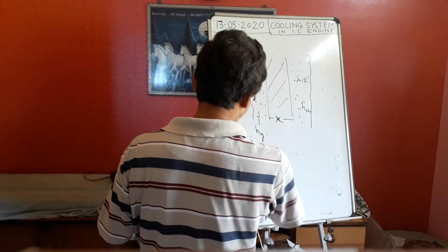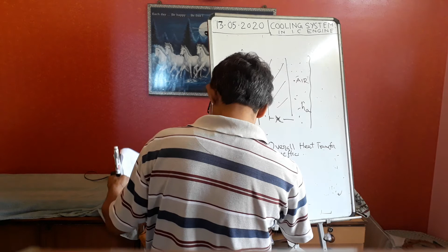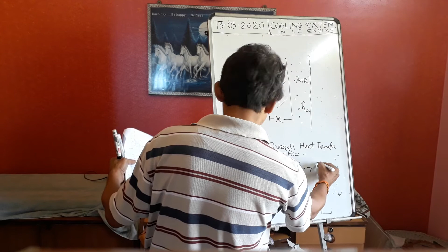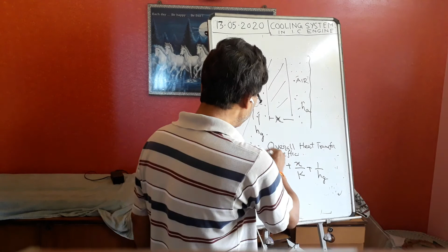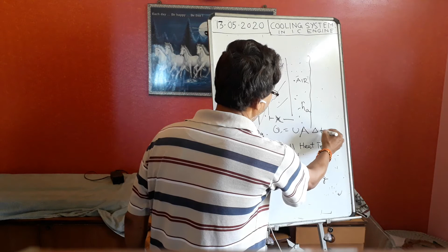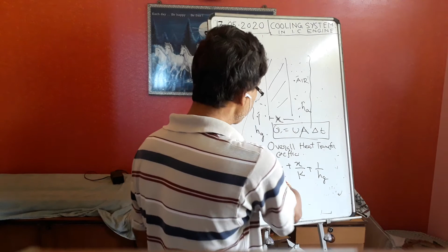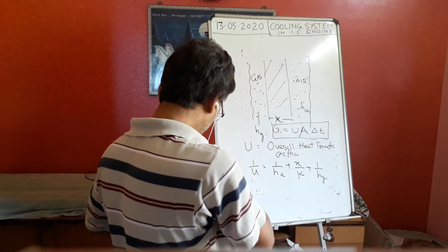U is called the overall heat transfer coefficient. In that case, 1 by U is equal to 1 by H_A plus X by K plus 1 by H_G. This way also we have to find out. In that case, we have to find Q is equal to U A del T, where U is the overall heat transfer coefficient. We have to find out the heat transfer coefficients in both the gas and the air film. Then we can design our coolant system.